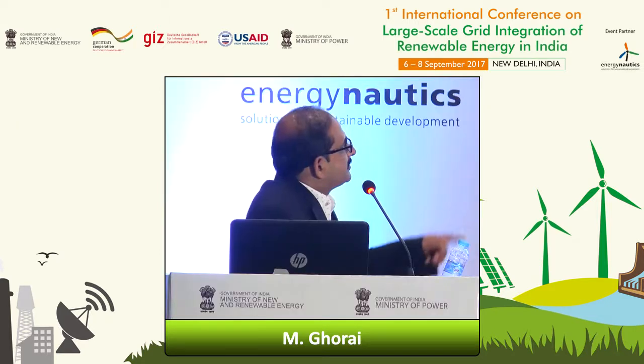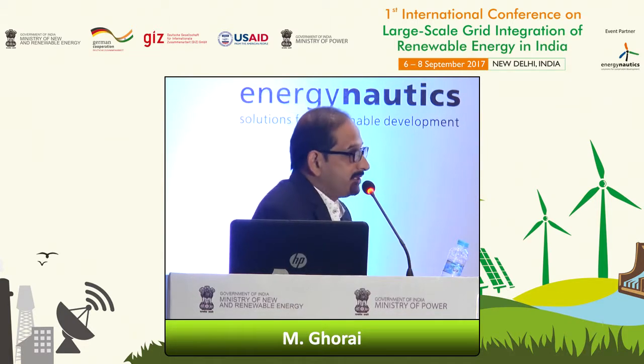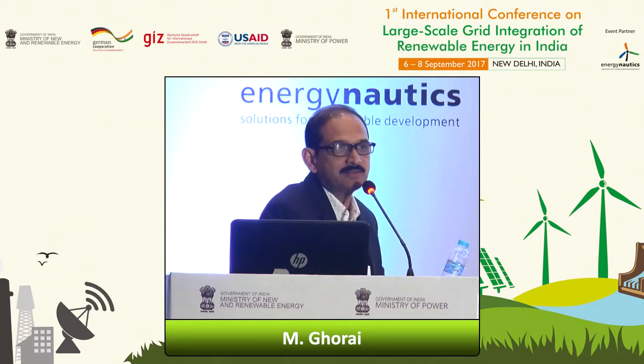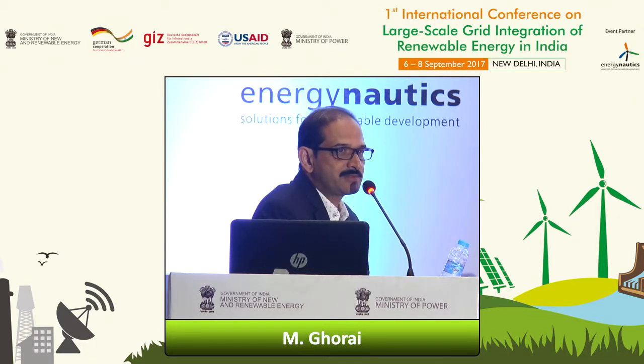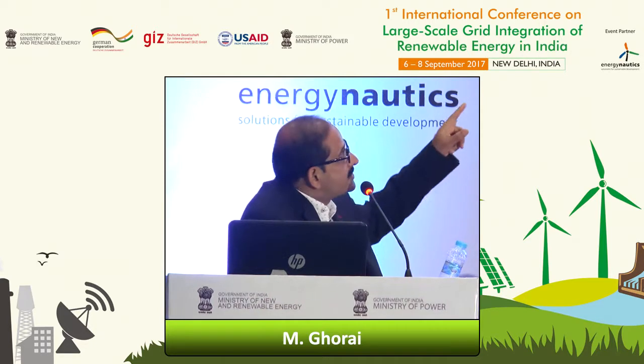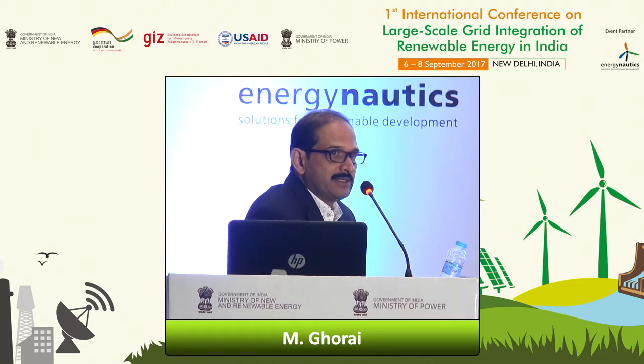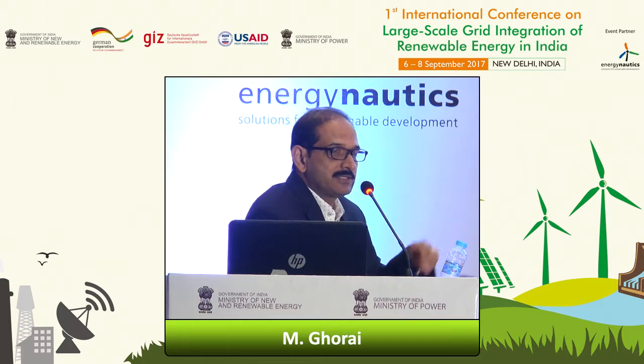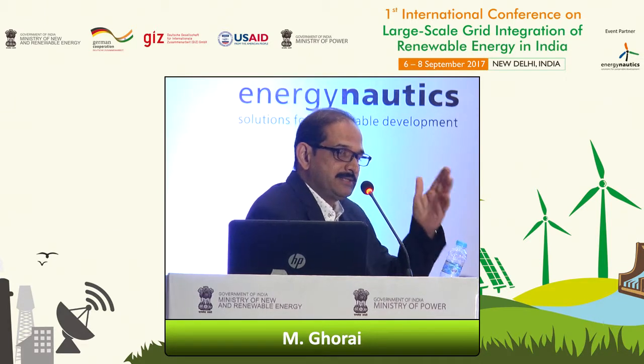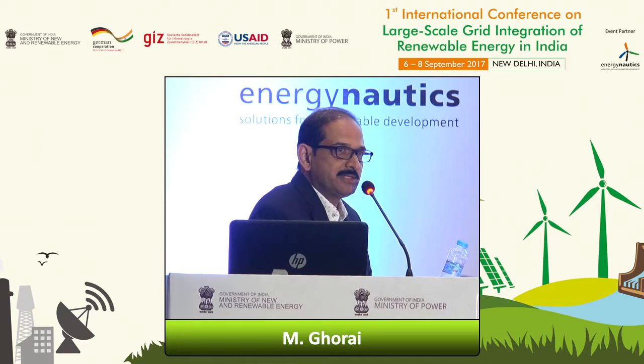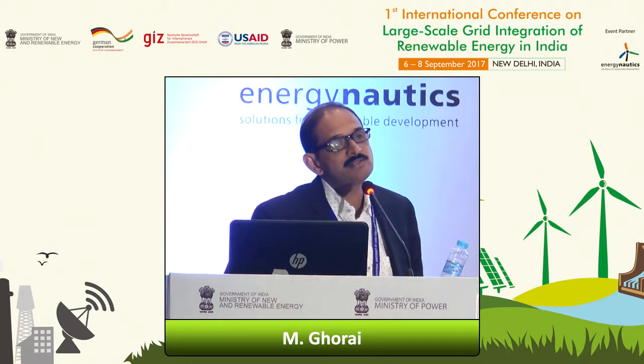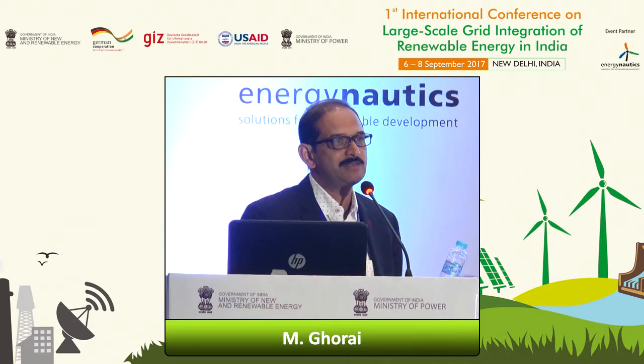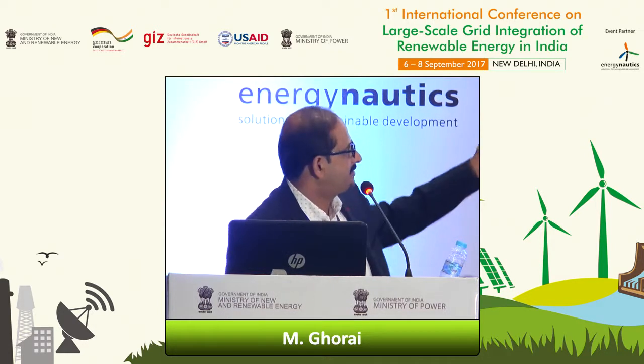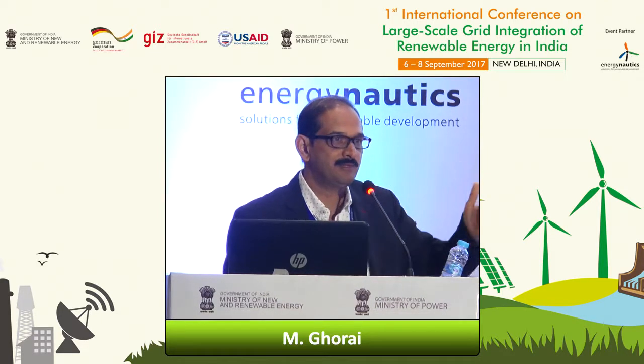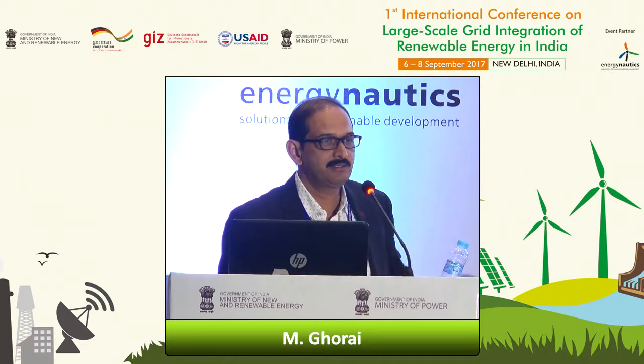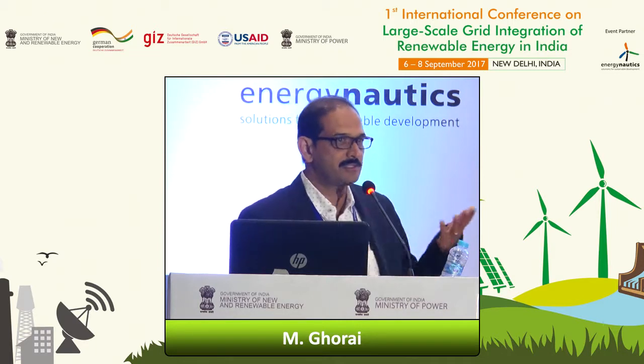What about that? So the STATCOMs are not at 132 kV. If you see our STATCOM, the output is 690 volts, and then we use a power transformer and connect it to the medium voltage. But what we do is we look at the point of connection and see that the grid codes are satisfied at that particular point. So the STATCOM connection at high voltage is not there. This is a medium voltage or a low voltage STATCOM. That's number one. Number two is that these can be provided in wind turbines, but then it's a cost economics. One has to see. The STATCOMs are provided at a wind farm level. A wind farm can have 50, 60, or 100 wind turbines. So it depends on the cost economics also.